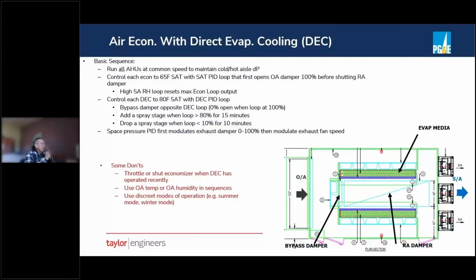So let's get into some of the details of air economizing with direct evap cooling. So here's some of the basics. We've seen some fairly complicated designs, and we think it can be really boiled down to something pretty simple. We typically run all air handlers at a common speed to maintain the cold aisle, hot aisle DP, right? We talked about that. So the air handlers are on some master control sent to all of them in terms of fan speed, but then each one controls individually for supply air temperature. So you'll control each economizer to an economizer supply air set point. We'll use, say, 65 degrees.